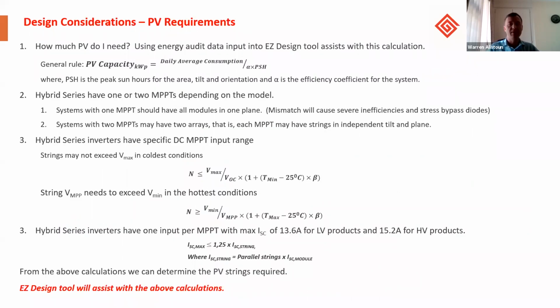Okay, so PV requirements. How much PV do I need? Once you've completed your energy audit data and you've worked out the average daily consumption, you can look at the general rule, which is that the PV capacity is equal to your daily average consumption divided by your efficiency factor times the peak sun hours for that specific tilt and orientation. These are calculations that you will not have to worry about when using our EZ Design tool. All of these calculations are handled through the simulation package, and none of these equations have to be put into Excel and done manually. This can all be done using the EZ Design tool.